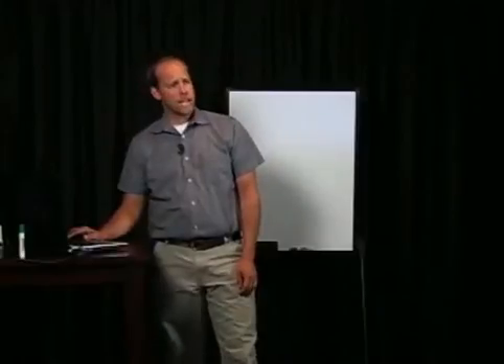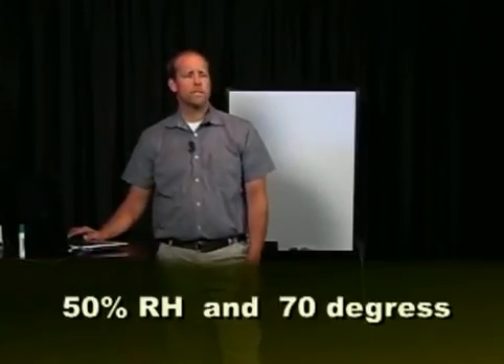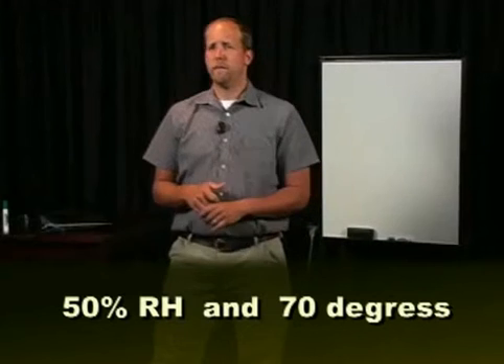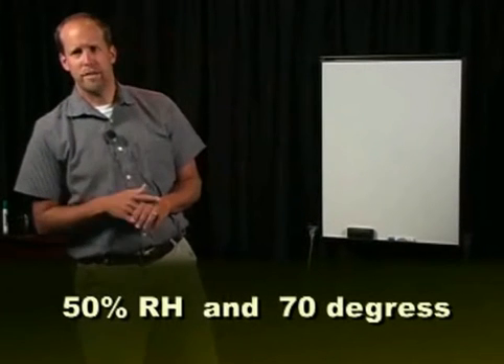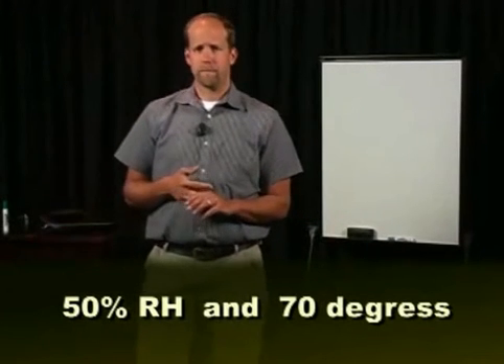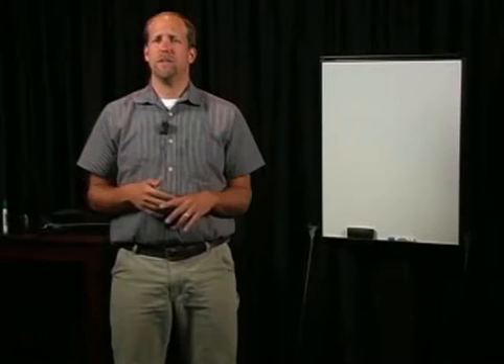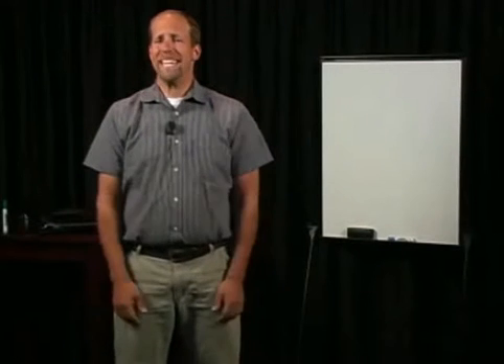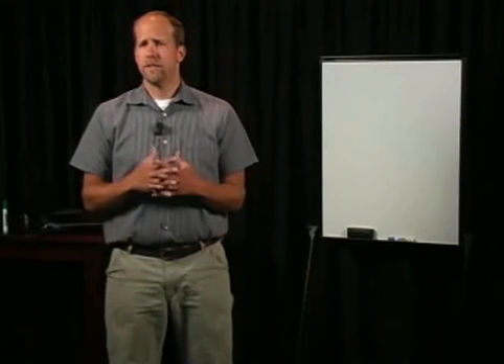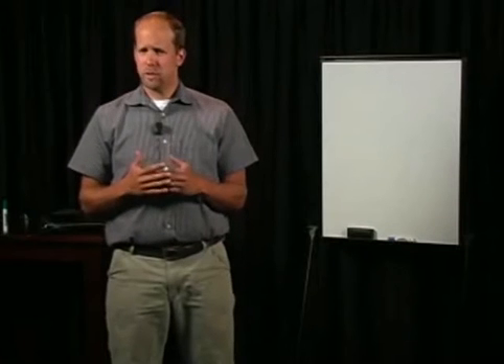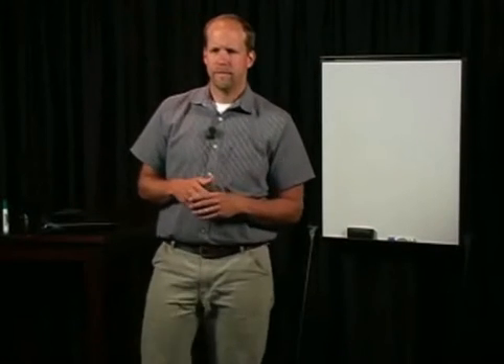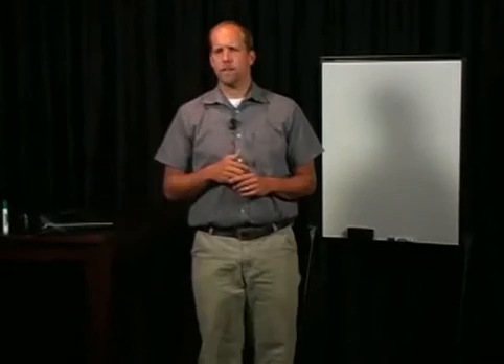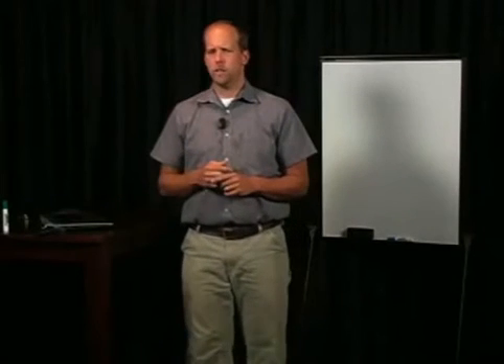In the second case, assume that the relative humidity is 50% and the temperature is still 70 degrees in the middle of the room. The higher RH at that temperature indicates that the water vapor pressure is high and there is a relatively large amount of moisture in the air. The high surface relative humidity is probably due to air that is too moist. Humidity is the dominating factor, and controlling strategies should involve decreasing the moisture content in the indoor air.